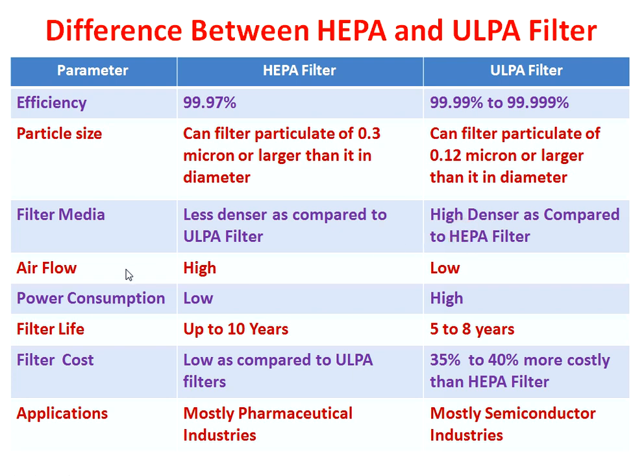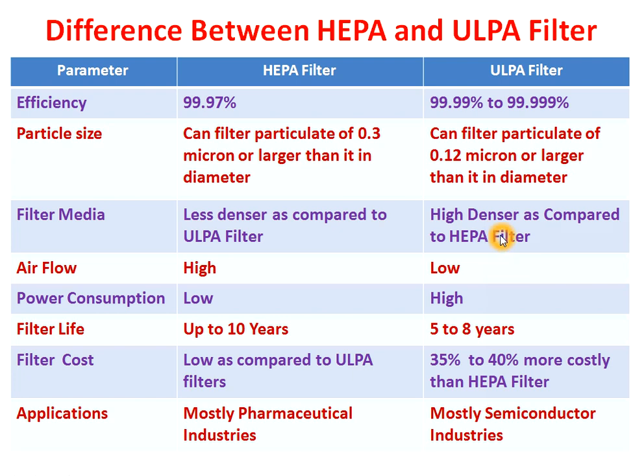Now for air flow: the air flow through the HEPA filter is high, whereas air flow through the ULPA filter is low. The reason is that the ULPA filter has high-density filter media, and with high-density media there is more pressure drop across the filter.